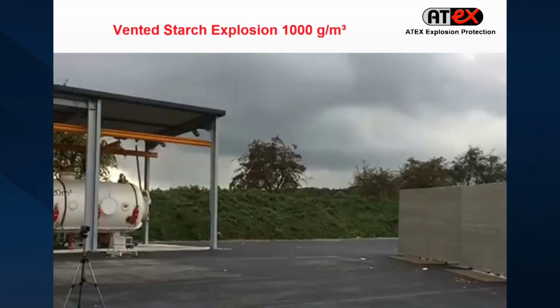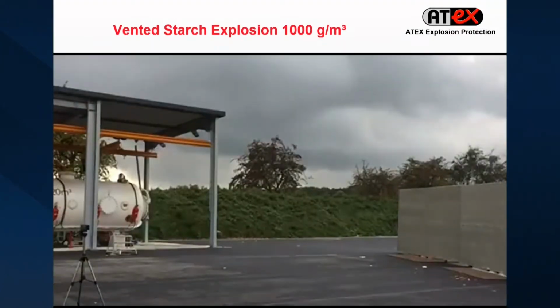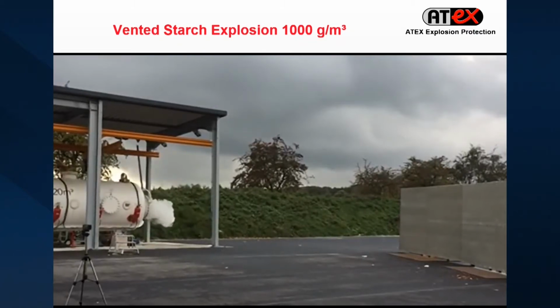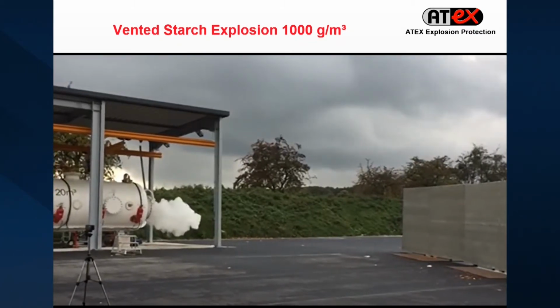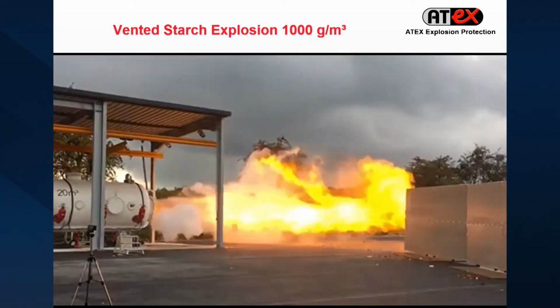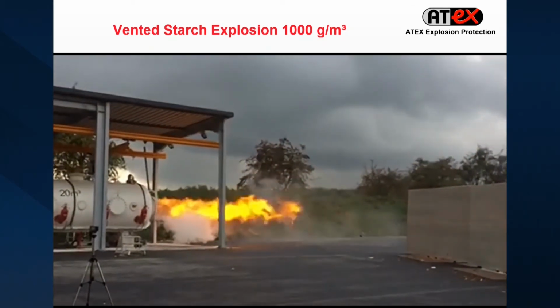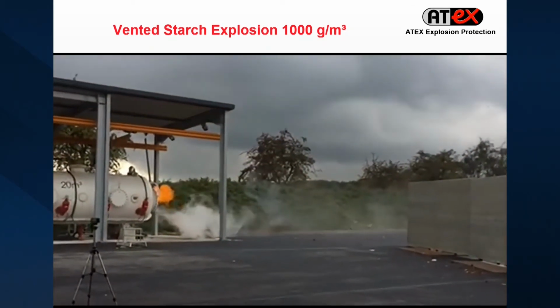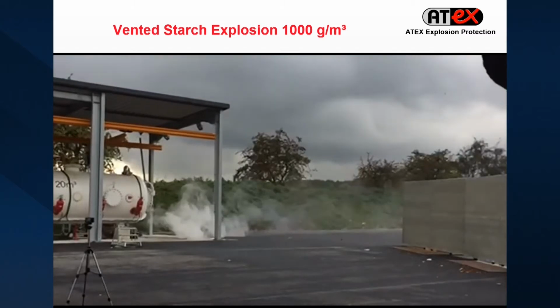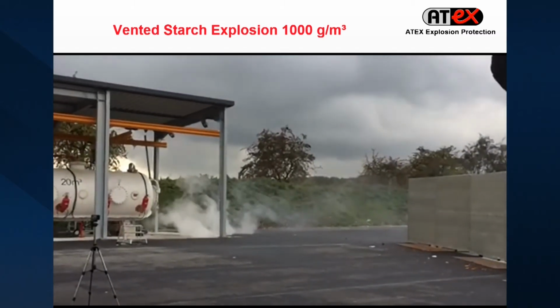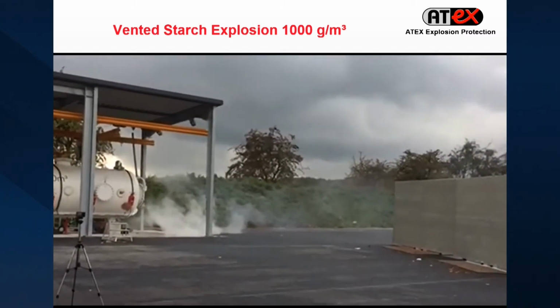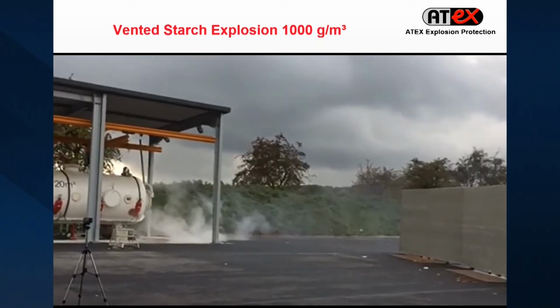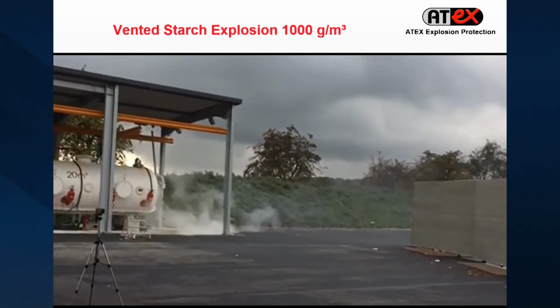And in the next experiment, we go from 250 grams to 1,000 grams, and that gives an even stronger explosion. You see that even the camera is shaking. But what we also wanted to see is, if we do these experiments, what kind of vent area we have to use and what influencing parameter we have that could cause an additional problem here.